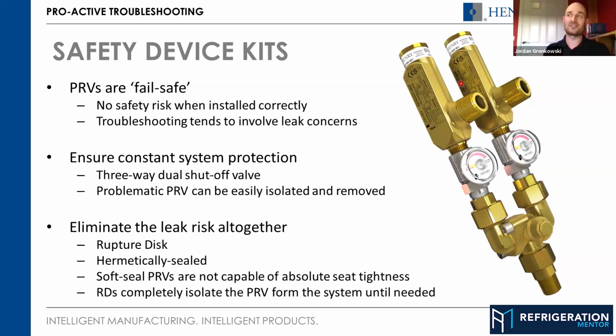So the beauty of a rupture disc is that you've got this hard seal. It's a hermetic seal. And what it does is it completely isolates the PRV from the system. So the PRV doesn't even see the gas. So it's the ideal solution because the PRV just thinks it's sitting on the shelf somewhere. So it's nowhere near the gas until it needs to see it, until it bursts. So the rupture disc bursts, the PRV goes at exactly the same time. Obviously, the rupture disc is gone, it's open, so the PRV is the thing that gives you the reseal again. And then you've got it on your 3-way valve, so you can easily switch the valve across, change it in for a new one, and no issue.